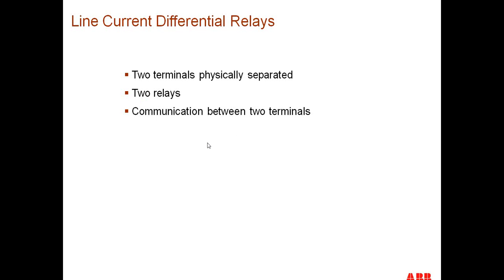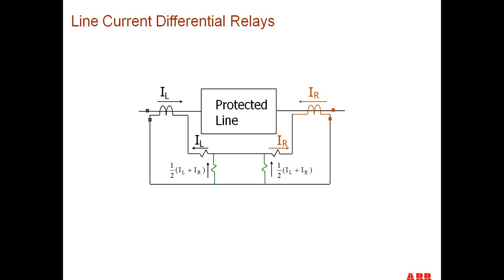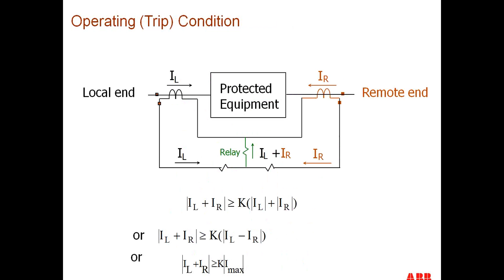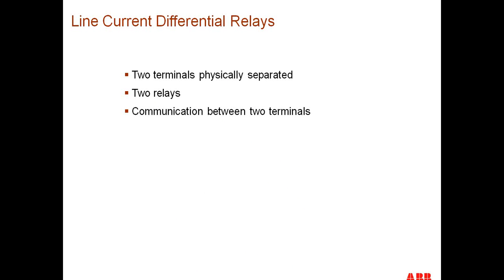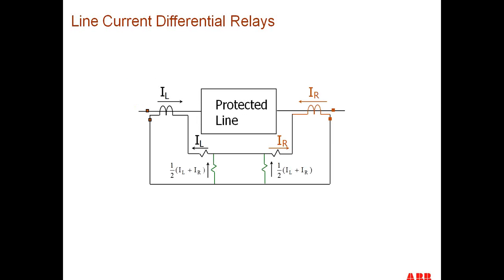Now, if we take that analogy of what we did for a transformer differential relay, and we expand it to a line current differential relay. In our previous relay, we had one relay that was protecting a piece of equipment. In our line current differential relay, now we have 2 terminals physically separated by some distance, anywhere from half a kilometer upwards of 200 kilometers apart from each other. So therefore, we have to have 2 relays, one relay at each end of the line, and some communication equipment between the 2 terminals, in order to make this comparison, or this differential circuit.